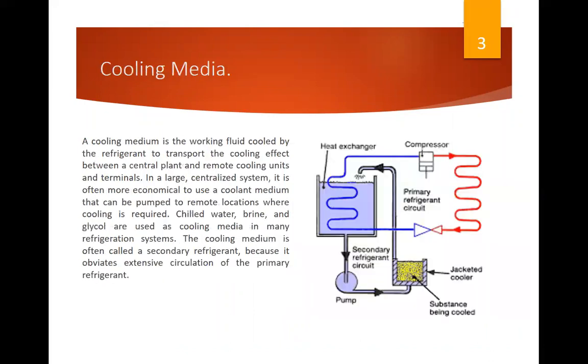Okay. Next is the cooling medium. The cooling medium is the working fluid cooled by the refrigerant to transport the cooling effect between the central plant and remote cooling units and terminal. In a large centralized system, it is often more economical to use a coolant medium that can be pumped to remote locations where cooling is required. Chilled water, brine, and glycol are used as cooling media in many refrigeration systems. The cooling medium is often called a secondary refrigerant because it obviates extensive circulation of the primary refrigerant over long distance.